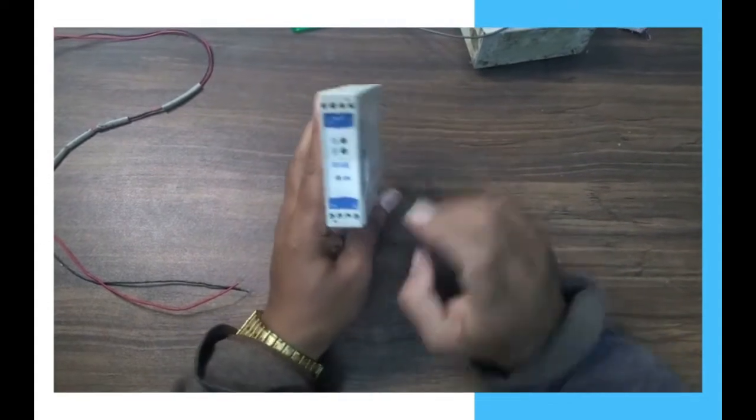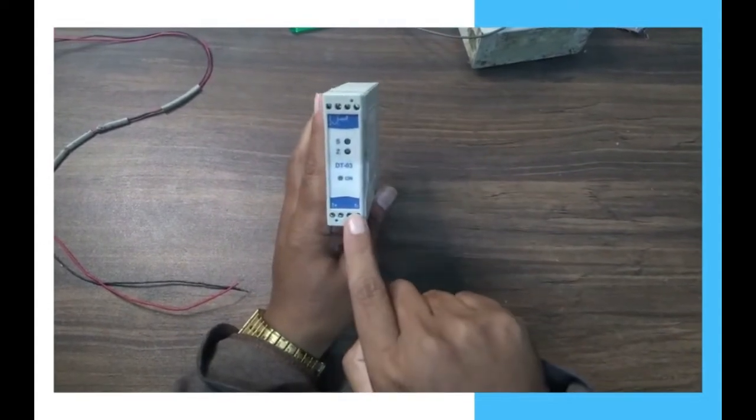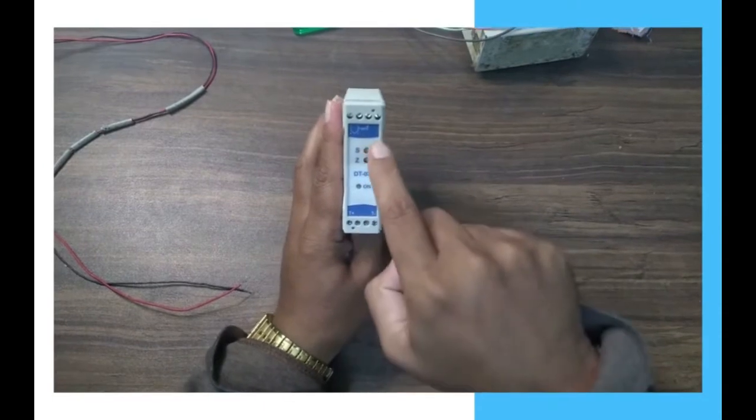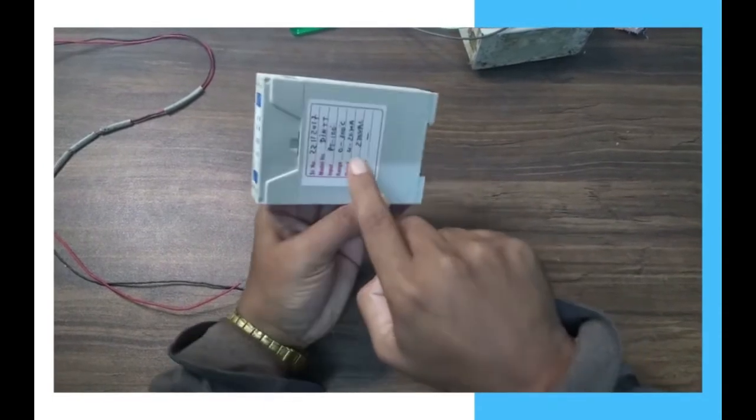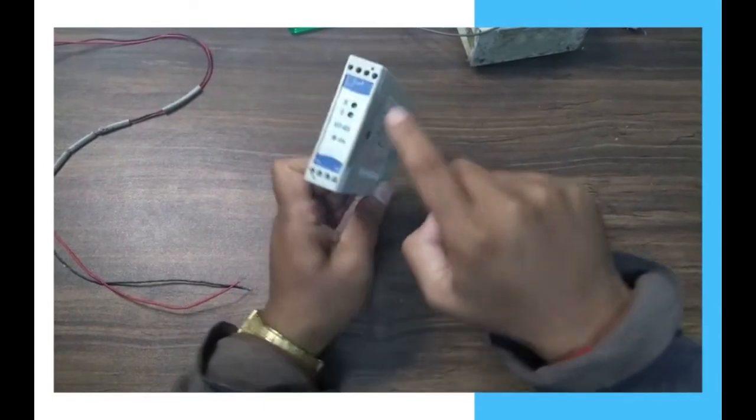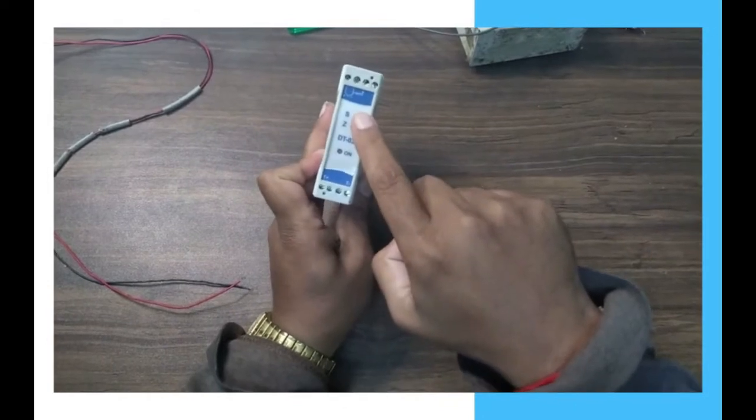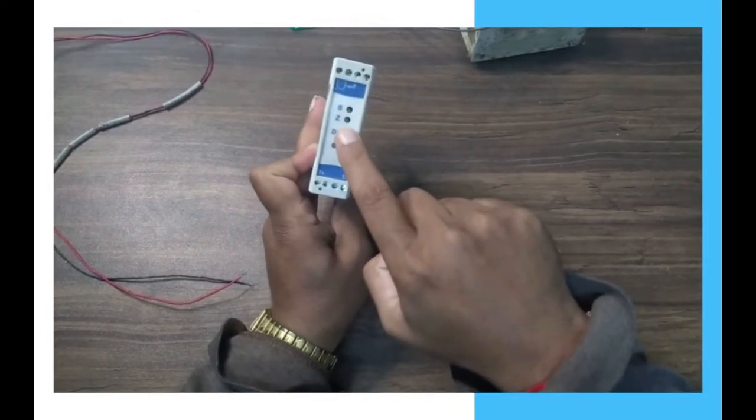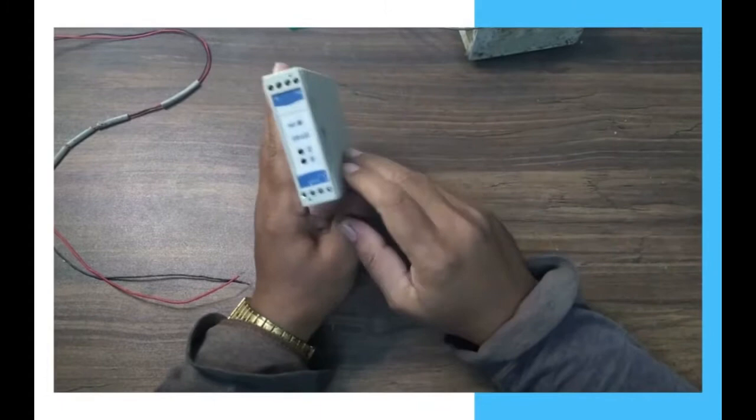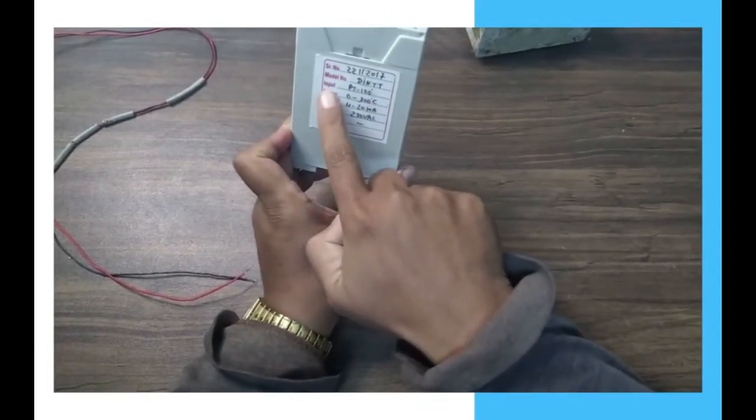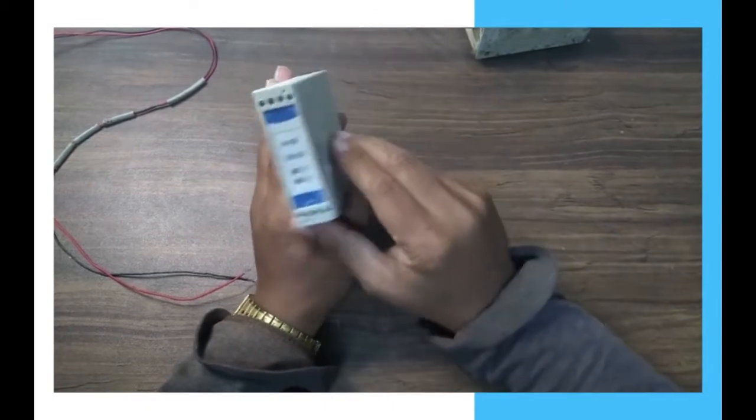Here we can apply 24 VDC power supply at the plus and minus terminals. This is a loop power device. Here, calibration ports for zero and span are also available. Zero means minimum value and span means maximum value. From this side, we can apply the RTD input.